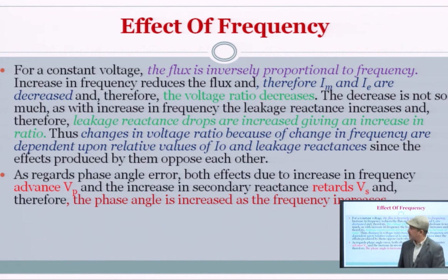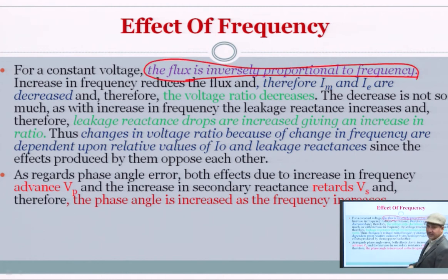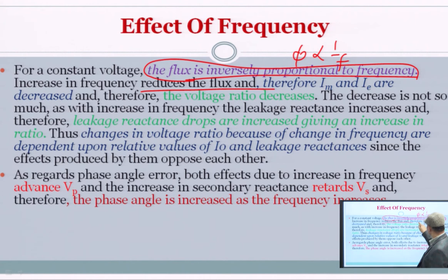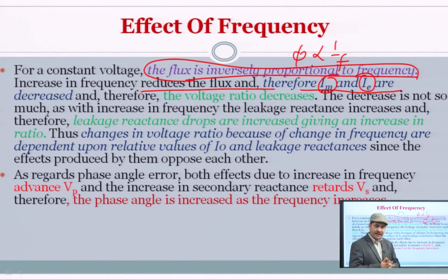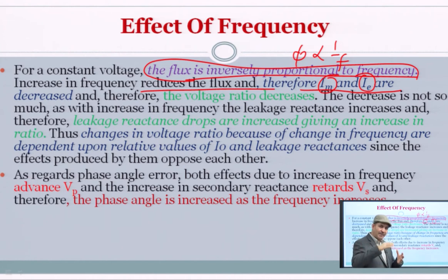Effect of frequency: for a constant voltage, the flux is inversely proportional to the frequency — flux ∝ 1/f. This concept was also discussed when we talked about current transformers. An increase in frequency will lead to a reduction in flux. Therefore, IM (magnetizing component) and IE (loss component) of the no-load current decrease. If IM and IE decrease, the ratio error improves — the error is minimized.